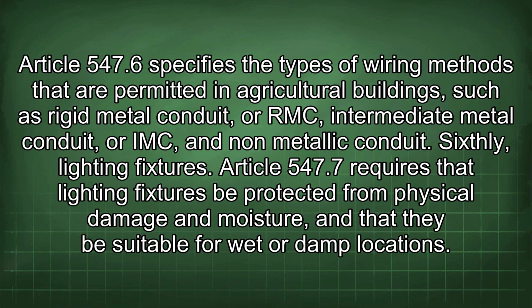Article 547.6 specifies the types of wiring methods that are permitted in agricultural buildings, such as rigid metal conduit, or RMC, intermediate metal conduit, or IMC, and non-metallic conduit.